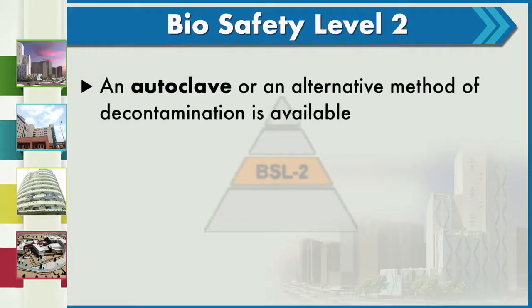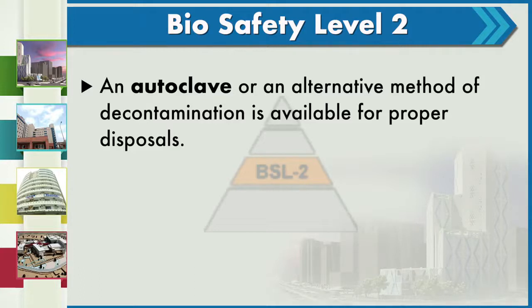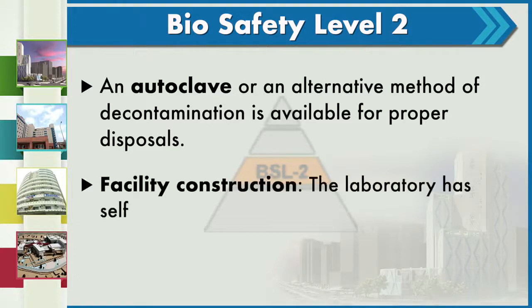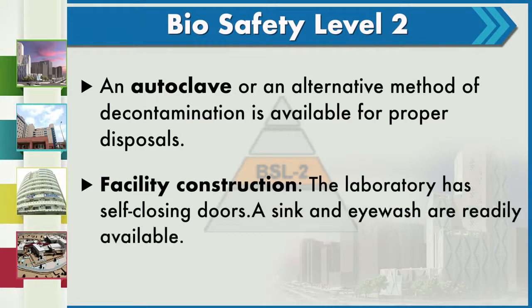Another important feature is the autoclave, which is an alternative method of decontamination available for proper waste disposal. For facility construction, the laboratory must have self-closing doors. As architects, facility managers, designers, and hospital administrators, you must ensure that a BSL 2 lab has an auto-closing door — a very small input that leads to a great amount of biosafety.